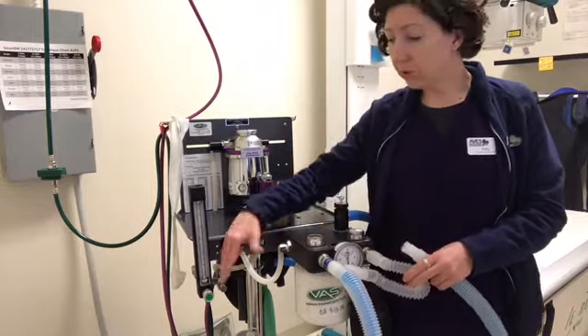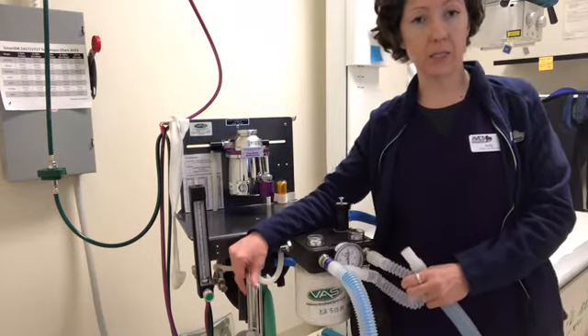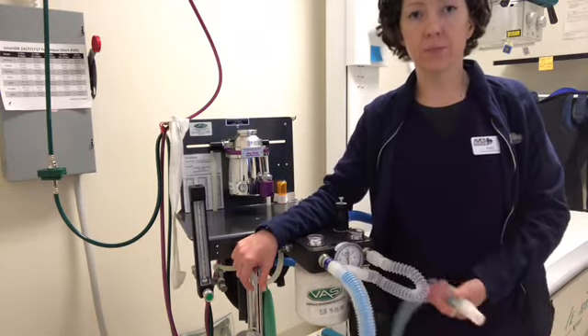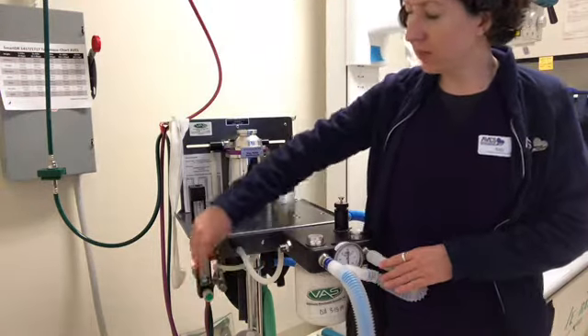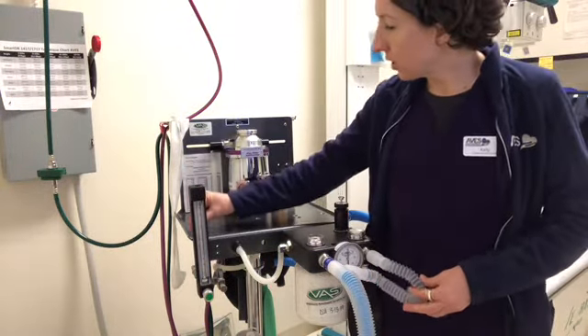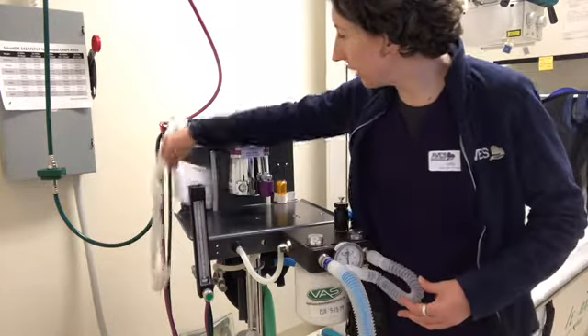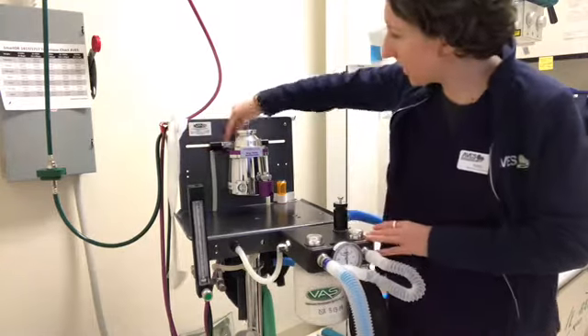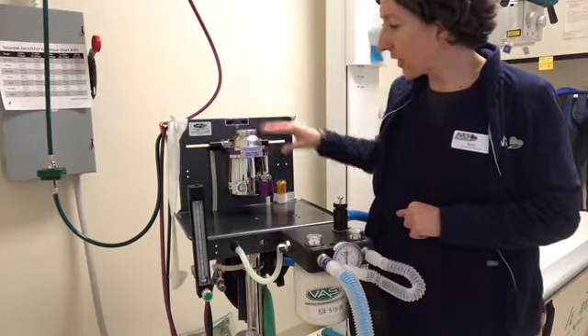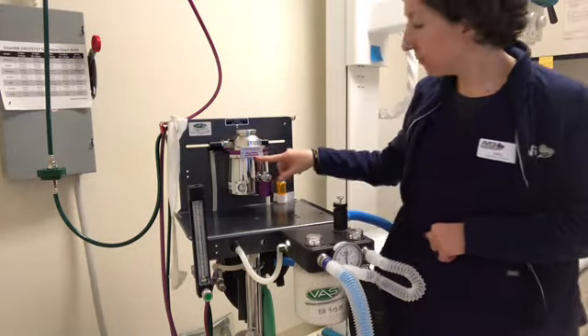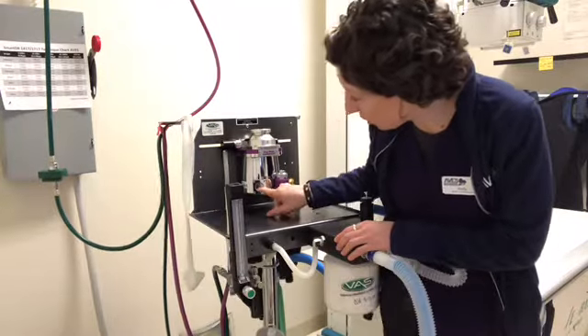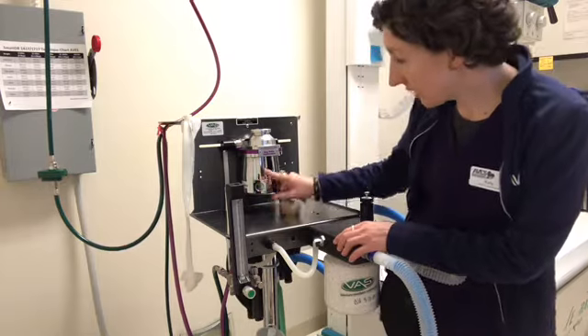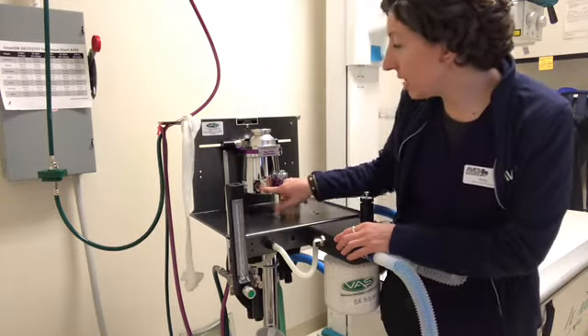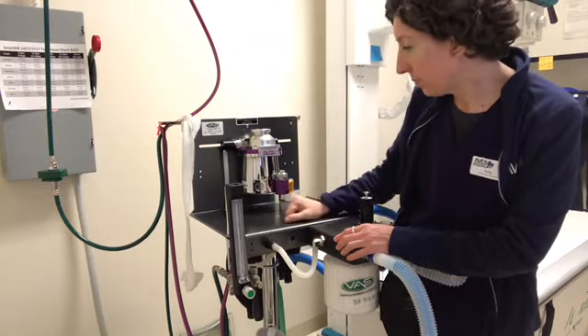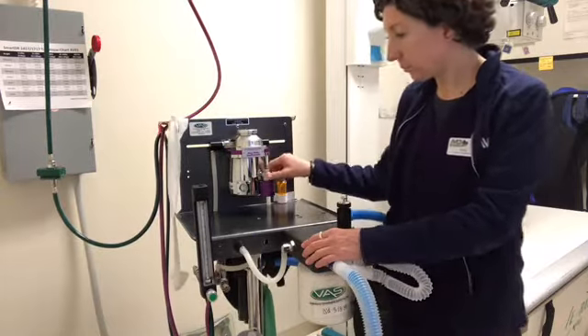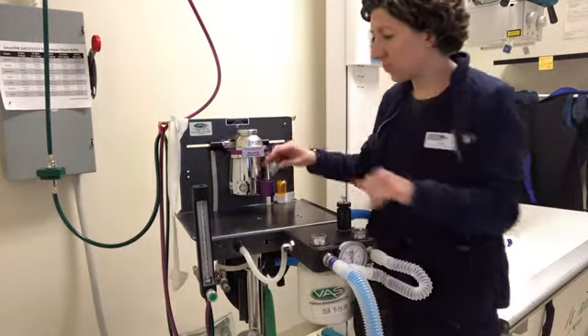And you would never want to use the oxygen flush valve when you're using a non-rebreathing system, because it could really damage the patient's lungs. Okay, so after the oxygen goes through the flow meter, it goes next to the vaporizer through the inlet port, which is right here, and then into the vaporizer. This is a precision vaporizer, and it is only to be used with isoflurane. Here is the little window that tells you what the level of isoflurane is in here. It needs to be between the two white lines, and it's about 3/4 of the way up. And to refill it, you would take this little screw top off and pour the isoflurane in there.